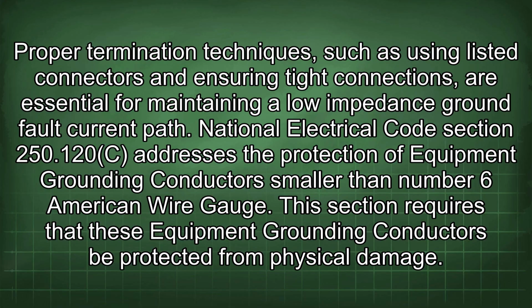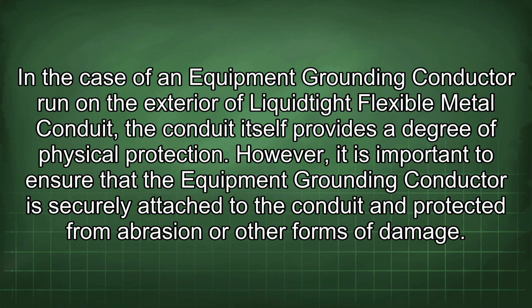National Electrical Code section 250.120(C) addresses the protection of equipment grounding conductors smaller than number 6 American wire gauge. This section requires that these equipment grounding conductors be protected from physical damage. In the case of an equipment grounding conductor run on the exterior of Liquidtight Flexible Metal Conduit, the conduit itself provides a degree of physical protection. However, it is important to ensure that the equipment grounding conductor is securely attached to the conduit and protected from abrasion or other forms of damage.